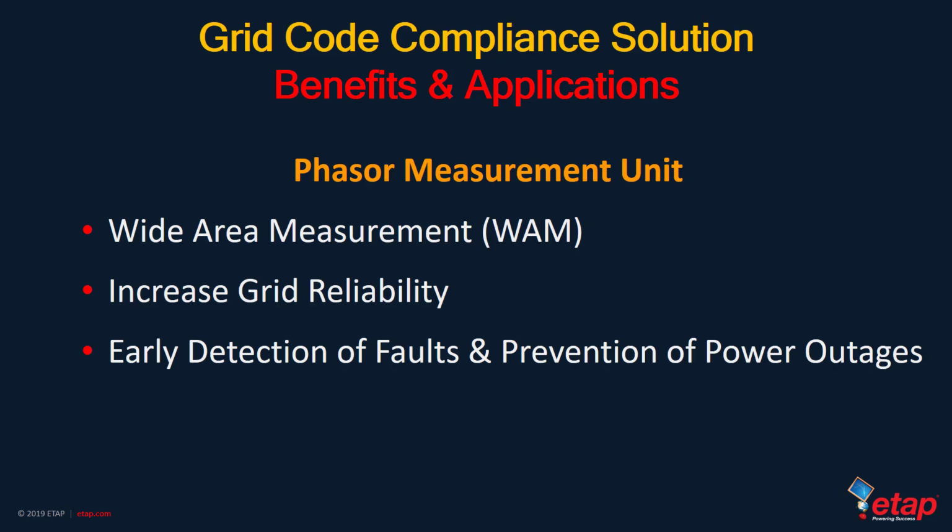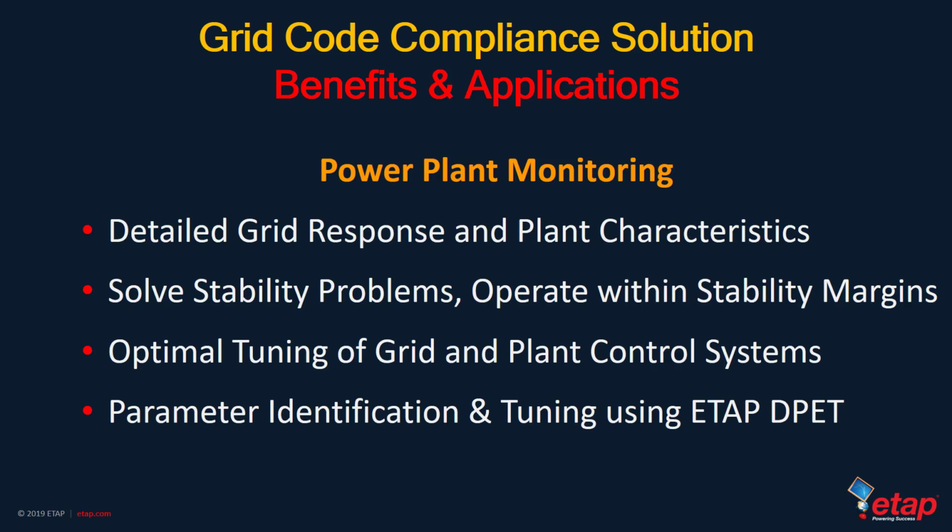The same recorder is also used for wide area measurement to improve grid reliability and early detection of faults in the network. You can of course use it for power plant monitoring that includes detailed grid response and plant characteristics, and of course for tuning the plant control, including compliance with the NERC MOD requirements for dynamic model tuning.